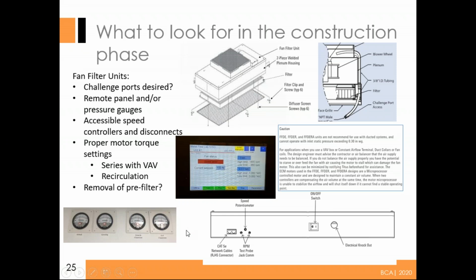so that they know the filters are getting dirty. For the balancers, make sure that this is on the side of the unit. If it's going to be manually controlled, make sure the potentiometers are accessible. Also check the proper torque settings of these fan filter units. If they are recirc, or if they're going to be tied in with the VAV box, the motor and torque settings on these ECM motors are different. So it's something to work out during the design phase or during construction. And all these fan filter units come with a pre-filter on the inlet side. Some manufacturers tell you to remove them, some tell you to keep them in place. So just be aware of that.